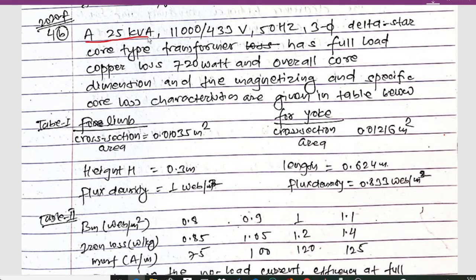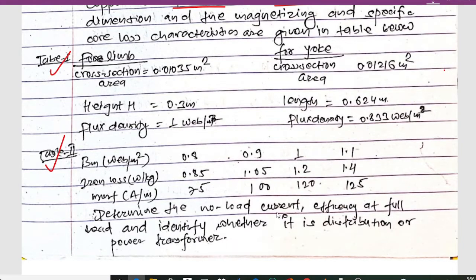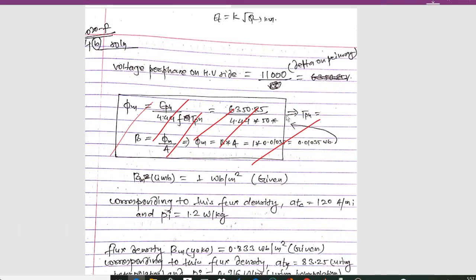A 25 kVA transformer is given here: 11 kilovolts slash 433 volt, 50 Hz, 3-phase delta-star core-type transformer. It has a full load copper loss of 720 watts. The overall dimensions and the magnetizing and specific core loss characteristics are given in the tables below — Table 1 for limb and Table 2 for yoke. We have to determine the no-load current, efficiency at full load, and identify whether it is a distribution or power transformer.